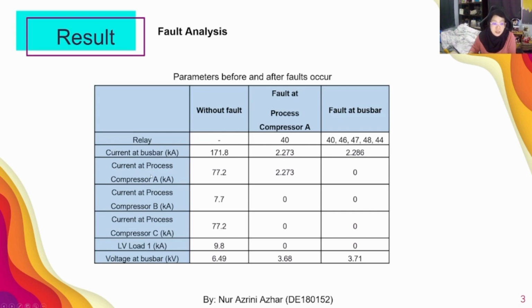For the next part, the current at process compressor A without fault presence is 77.2 kiloamp, the current at process compressor B is 7.7 kiloamp, and the current at process compressor C, without any fault presence, is 77.2. Last but not least is the voltage at the bus bar in kilovolt, which without fault presence is 6.49 kilovolt, while for the fault occurred it is 3.68 and 3.71 respectively. So the voltage drop is quite high, almost 50%. That's all from me.